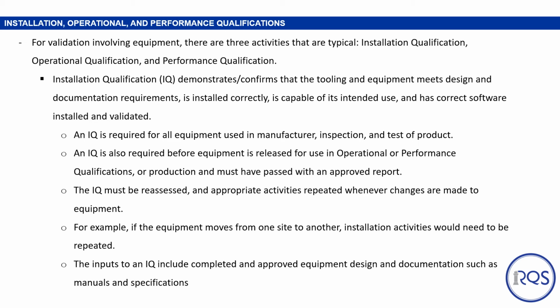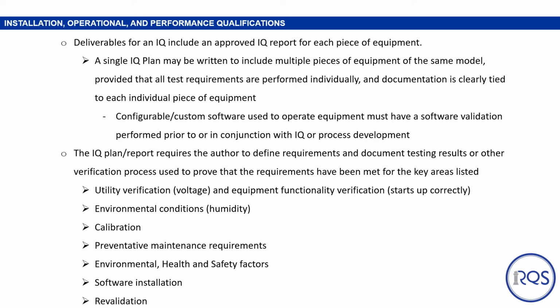The inputs to an IQ include completed and approved equipment design and documentation, such as manuals and specifications. Deliverables for an IQ include the IQ report that is approved for each piece of equipment. A single IQ plan may be written to include multiple pieces of equipment of the same model, provided that all test requirements are performed individually and documentation is clearly tied to each piece of equipment. Configurable custom software used to operate equipment must have its own software validation performed prior to or in conjunction with the IQ or in the process development.